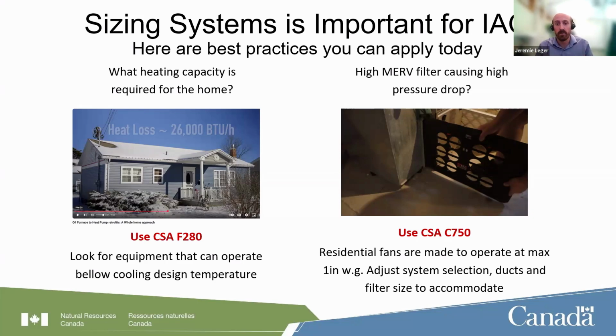The next piece is making sure you're not stressing your equipment with too much pressure if you're moving to a higher MERV filter. Using CSA 750, a new standard just published this month, we'll be able to look at residential ductwork and airflow. Having numbers on airflow and pressure will enable you to adjust system selection—maybe pick a smaller heat pump or system with lower airflow requirements, or adjust some ductwork as part of the retrofit to accommodate more airflow and the filter size.